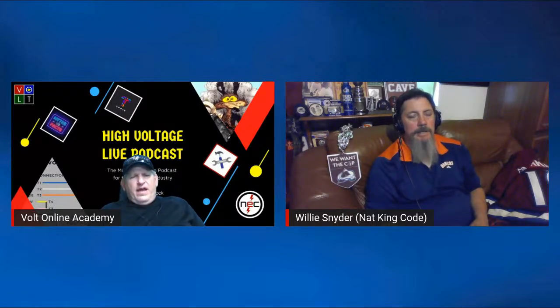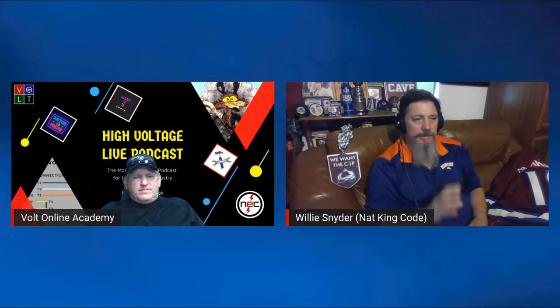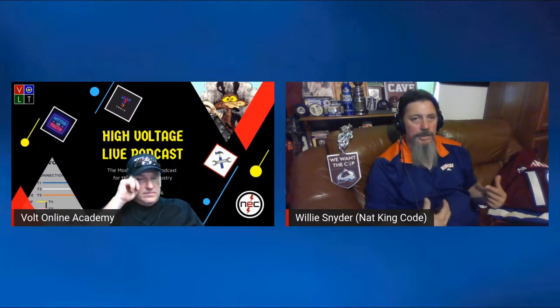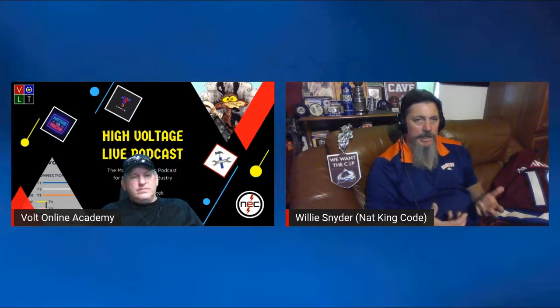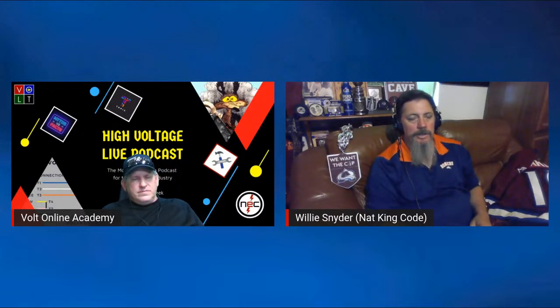Typically what these guys do is leave the disconnect energized and won't even go open it. They'll just open the unit while it's energized. So it's not really the electrical worker that's in the danger zone - it's usually the HVAC equipment guy or whoever's servicing the equipment. That's going to come in with 70B, so we might be able to tie a little bit of that in too.